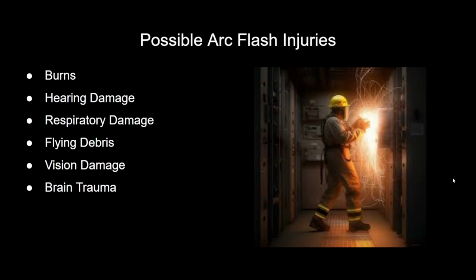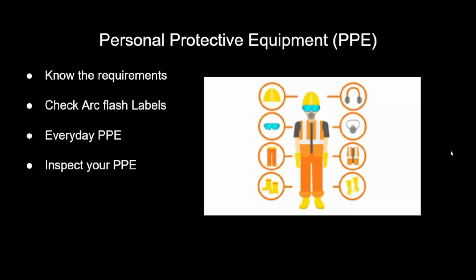Some possible arc flash injuries: burns from the explosion, hearing damage from the noise of the explosion, respiratory damage when the metal parts inside vaporize and you breathe that in, flying debris, vision damage, and even brain trauma from flying parts. PPE, personal protective equipment. Know the requirements. Make sure you're checking the arc flash labels, know what you've got to wear. I'm going to talk a little bit about everyday PPE, and make sure you're inspecting your PPE. No one else is going to check your stuff for you. It's on you to make sure you're being safe.